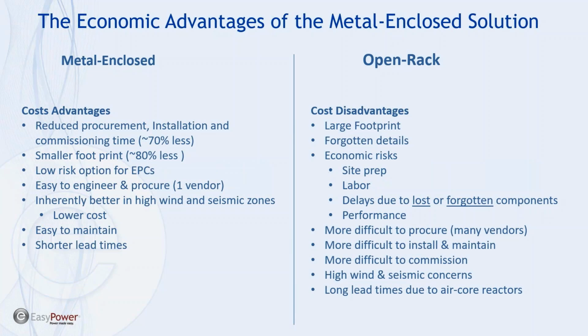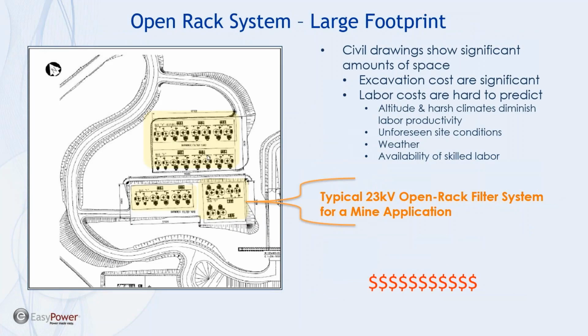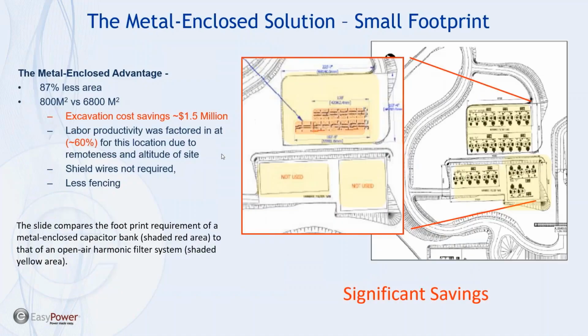Footprint. The metal-enclosed solution is just 80% less in footprint area. And this can carry a significant cost. And I show by way of example here, a typical 23 kV open rack harmonic filter system for a mine application. The shaded yellow area here represents the amount of area required to install this harmonic filter system. Okay, we compare that to the metal-enclosed solution. We've taken this area here and we have decreased it to just this area here.